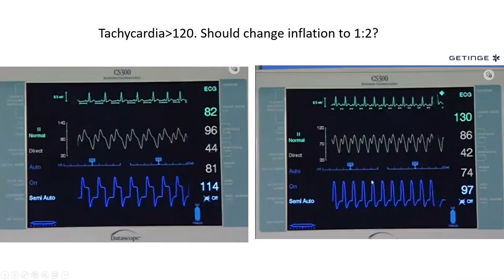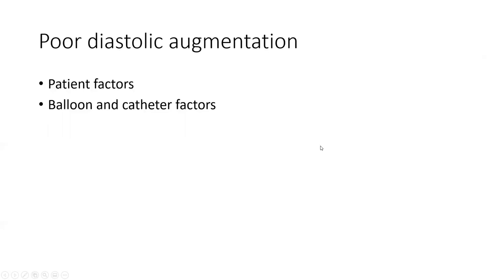Now, another idea with tachycardia is that you get less diastolic time. Therefore, you get less time for the balloon pump to displace the blood volume in diastole, and therefore you get less diastolic augmentation. You have less time for that augmentation to rise further. You get less augmentation, and therefore you get less vacuum upon deflation and less reduction in afterload. Okay, so that's why you get less augmentation with tachycardia. That's why tachycardia is harmful. If you go to 1 to 2, you'll actually compound and aggravate the problem. So definitely don't do that.